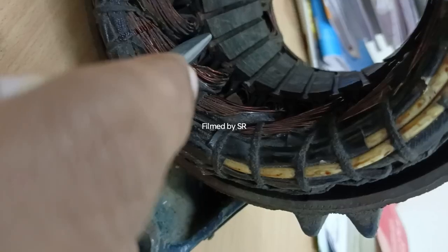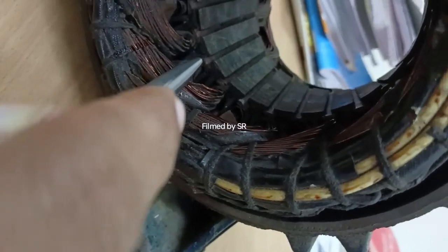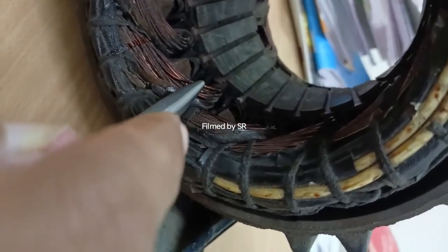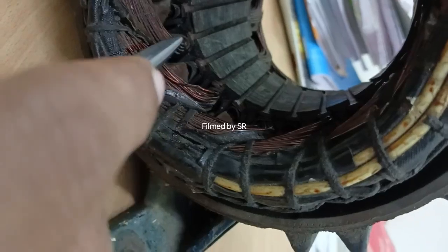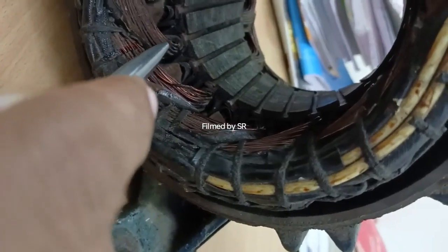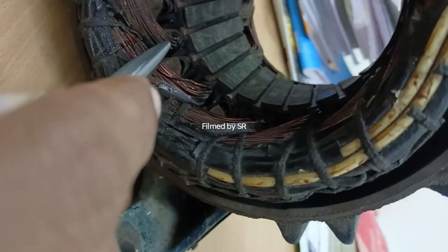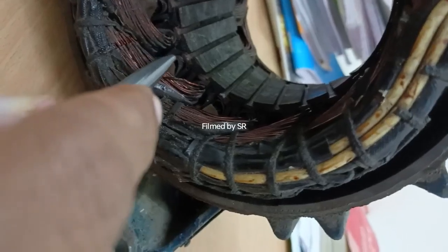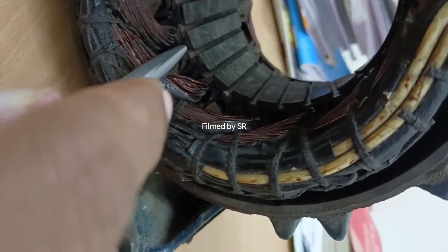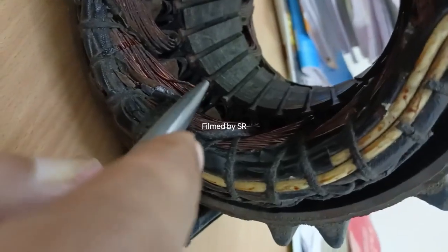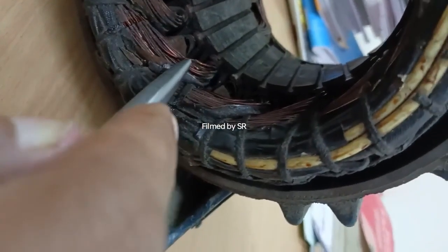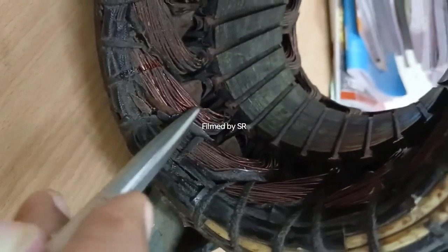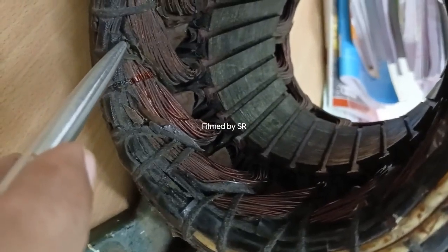Secondly, this will also ensure that you have mechanical ruggedness of the entire structure, because if you place a certain number of coils all in the top layer, then there is a chance that they may get dislocated when the machine is running or in vibration. But when you place it in this manner, you have the top layer and then it goes to the bottom layer, right? You can see it from here, it goes to the bottom layer, right?